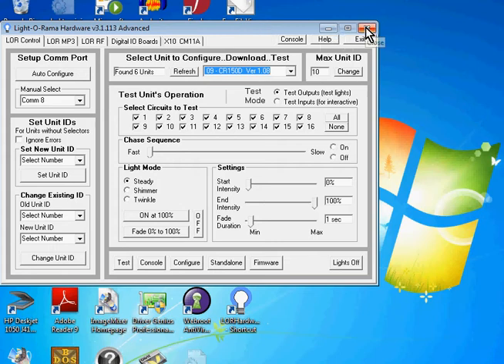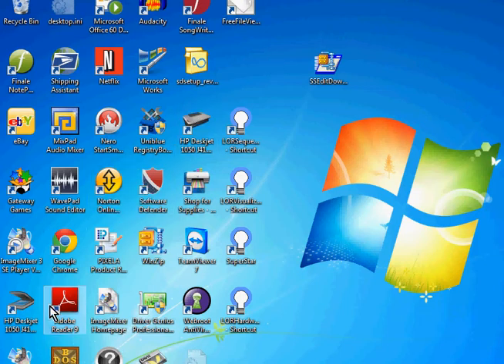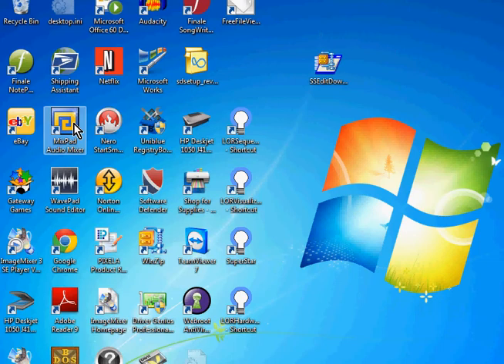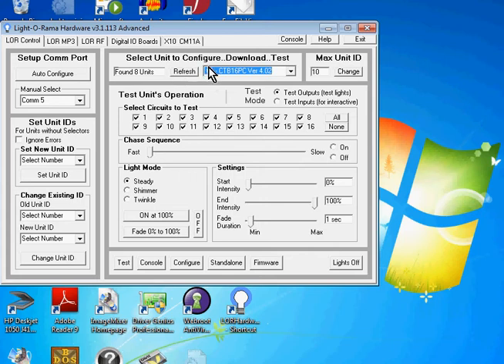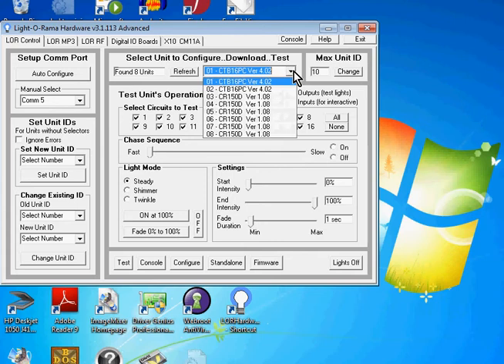Now an interesting thing about these USB 485 adapters is I just shut down the hardware utility and I am switching the USB port that the adapters are plugged into. And you would think that that would switch the COM number that is associated with each network. But here we have COM 5 selected there and if we hit on refresh, contrary to what you might expect, you'll find that COM 5 is still associated with the standard network because you see it still found eight units on COM 5 and it is the two 16 channel controllers and the first six CCR controllers.